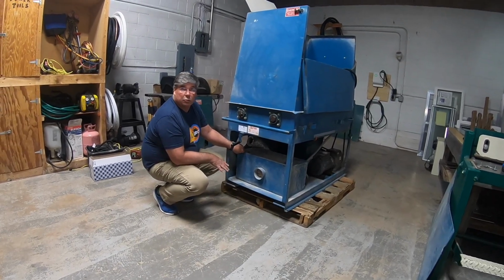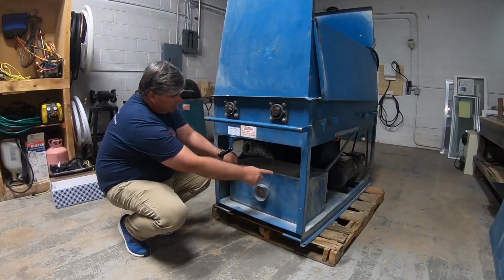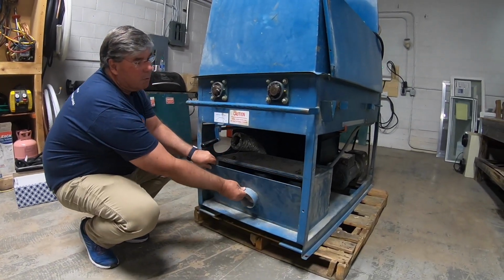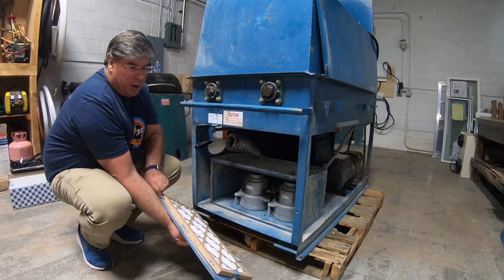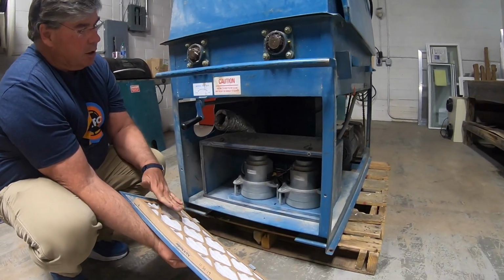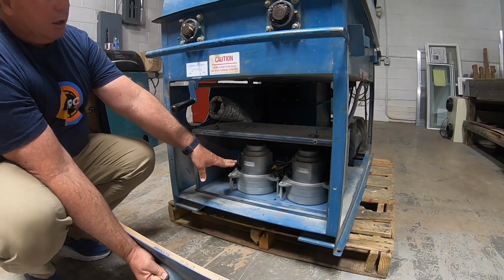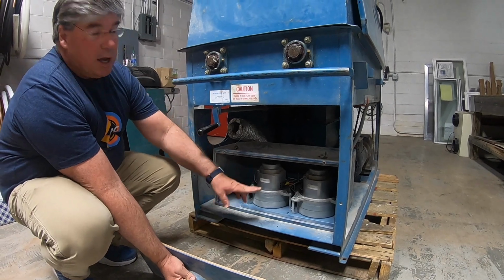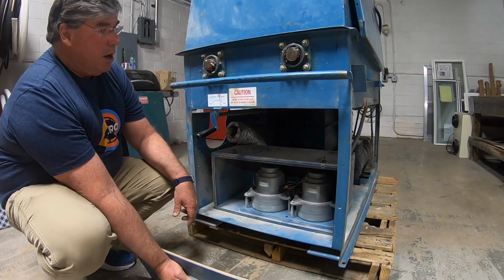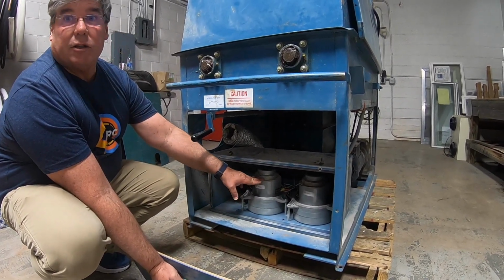One of the other things we take care of down on the bottom here: take the 2 bolts out, pull this panel out, and lift up. There's an air filter here, so we change the air filter. The other thing I'd recommend is blowing out these motors in this cage with compressed air—it helps extend the life of these motors.